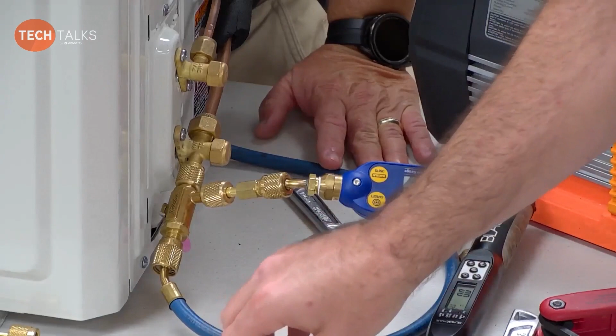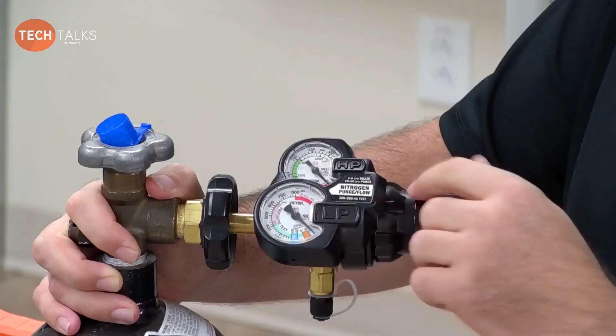So on the example we have here, on our nitrogen tank, Greg brought this awesome regulator. That's a pretty cool regulator. I do like it. Mine is just the regular style, but this one has the purge and flow on here. So all you have to do is crank it in, and it'll set to either purge, or you can set it to flow and put it at really high pressure, up to 500 pounds.